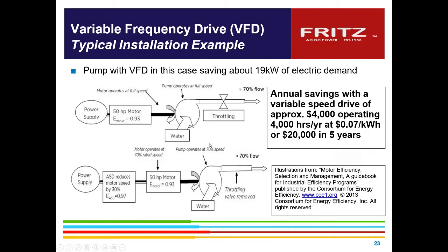So, the annual savings with and without a drive, this happened to be a case of a 19 kilowatt savings, that had a pretty good return of almost a $20,000 savings, and that was on a 50 horsepower motor. And when they put it with the VFD, we were able to save almost $20,000 over the 5 years, which is back to the loss factor in the motor.